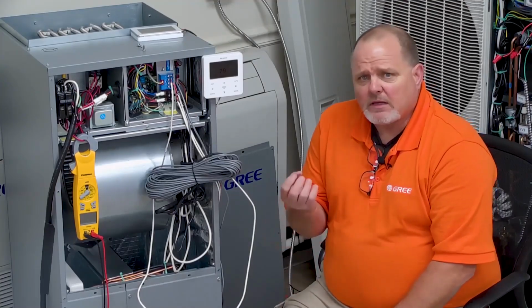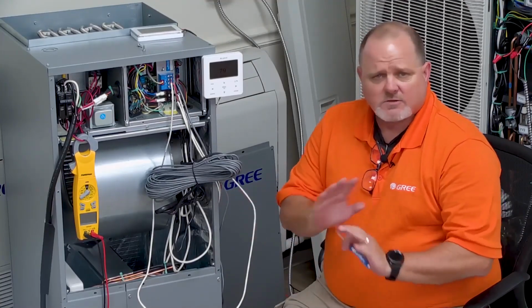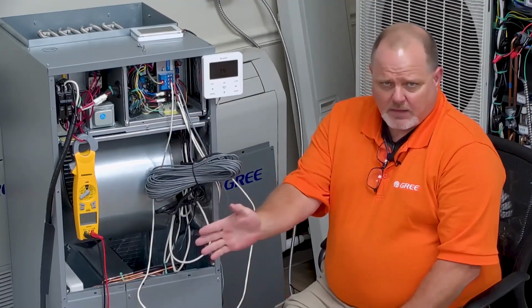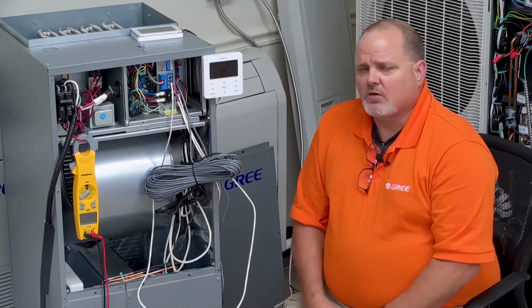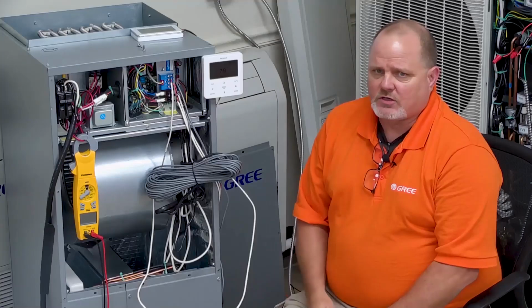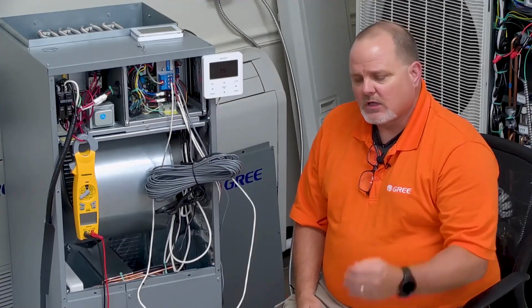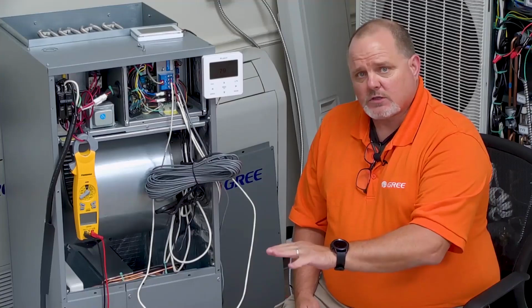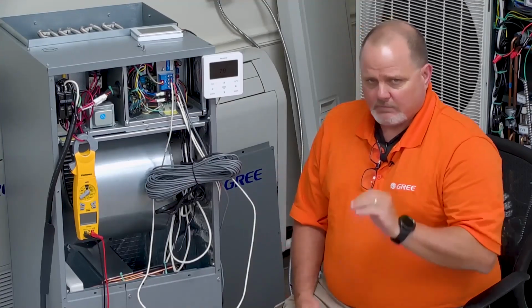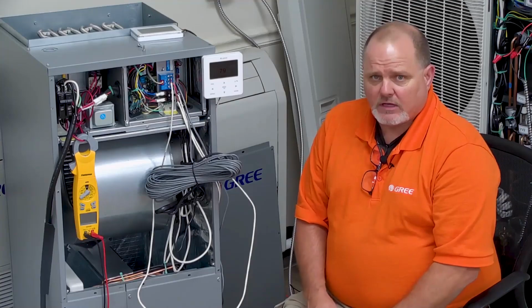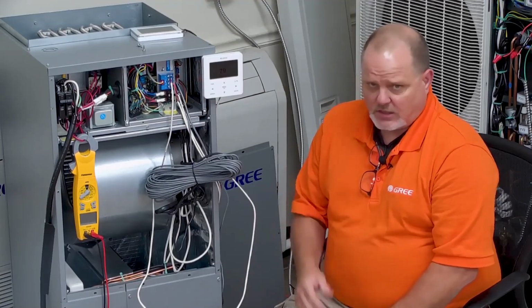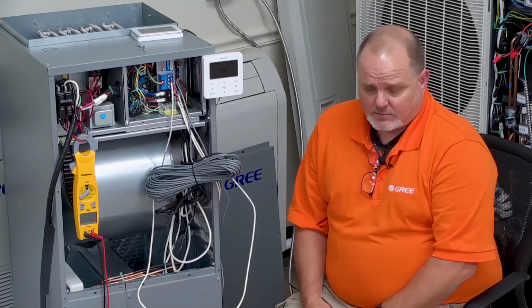Emergency heat is exactly that. If the heat pump is dysfunctional for whatever reason, whether it's a MultiPro heat pump or any other heat pump, if it's out on an error code, can't defrost properly, whatever the case may be, the emergency heat function gives us the ability to set it to emergency heat, or GREE likes to call it E-heat function. By putting it in E-heat function, the heat pump no longer functions until it gets serviced and repaired. The E-heat function gives them the ability to still have heat in the house, running just the electric heat until the serviceman gets there to fix it.